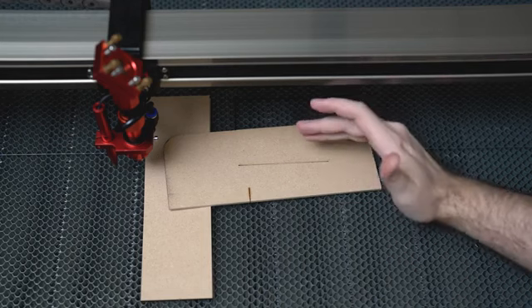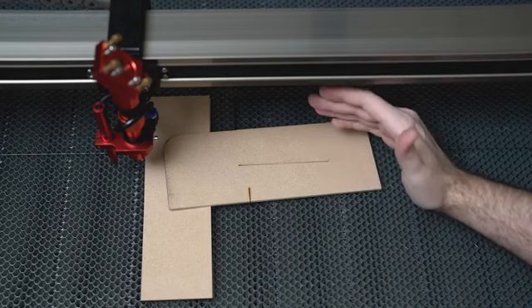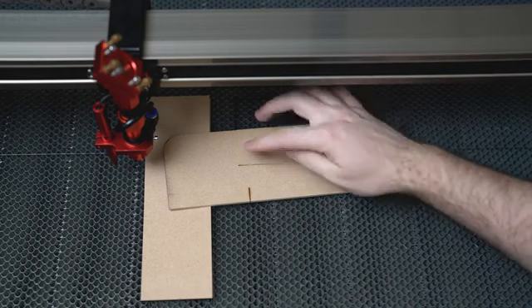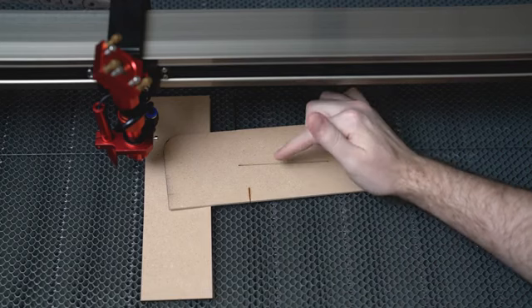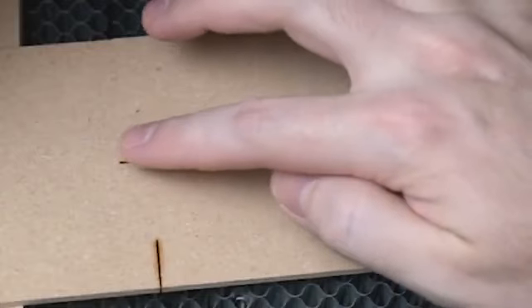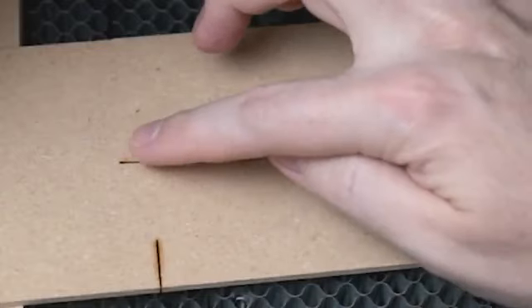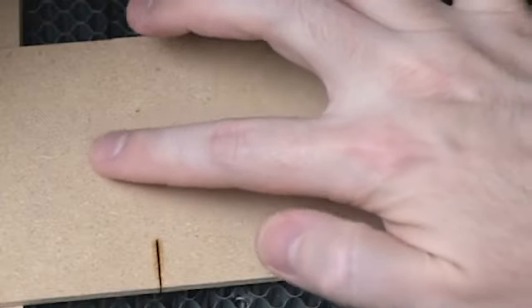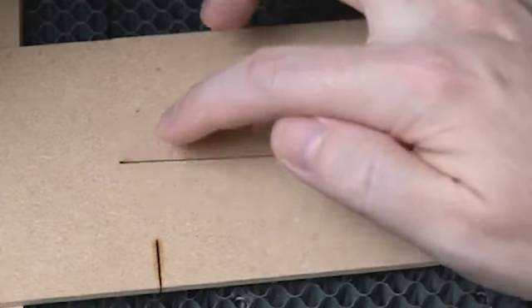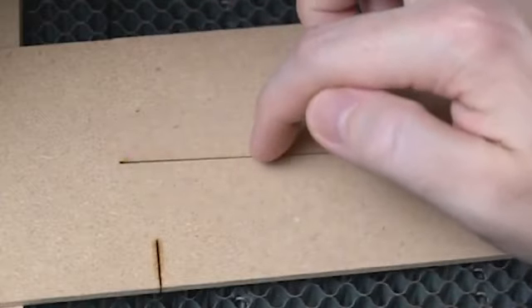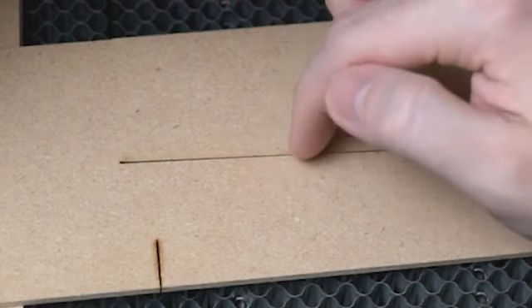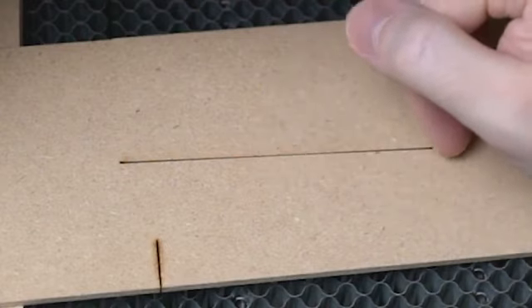So what we're able to observe with the outcome of this test is where the focus is on your laser. And we can see that as the line progresses down here, the laser is out of focus right here at the top. You can see the line is thick. As it progresses down the ramp, it becomes thin, and then as it goes even further, it becomes thick again.